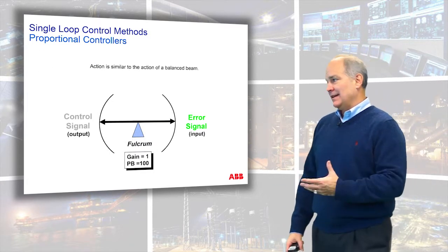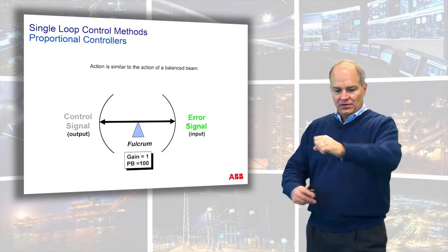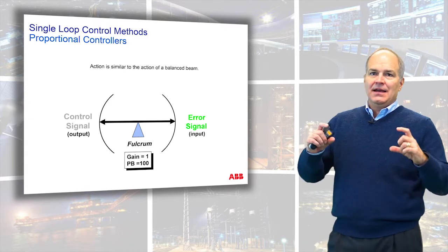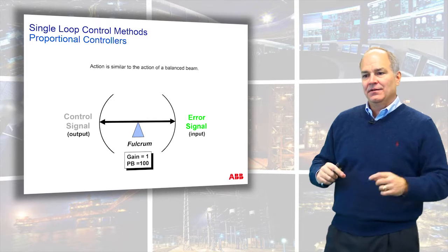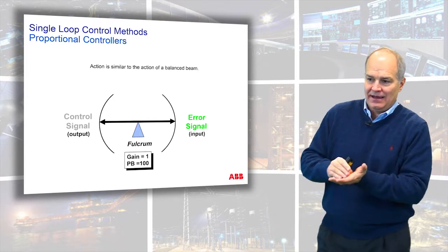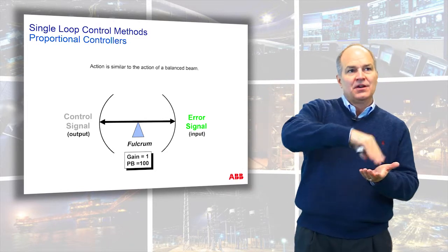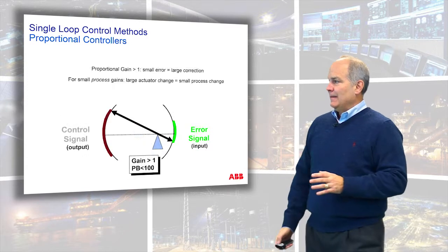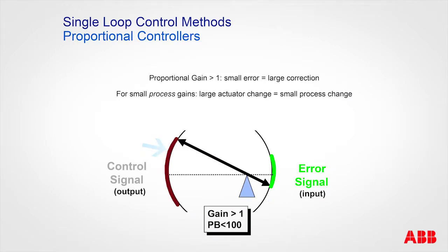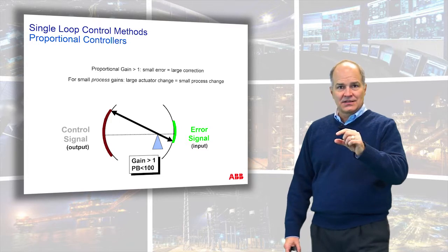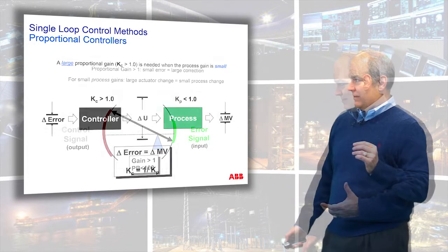The teeter-totter analogy really helped me understand the fulcrum and pivot point, where the pivot point is your gain. With a gain of one, or a proportional band of 100, a 100% change in error produces a 100% change in output — they're matched. If the gain is greater than one, the error doesn't have to move very much and the output moves a lot, like a large actuator that produces only a small process change.